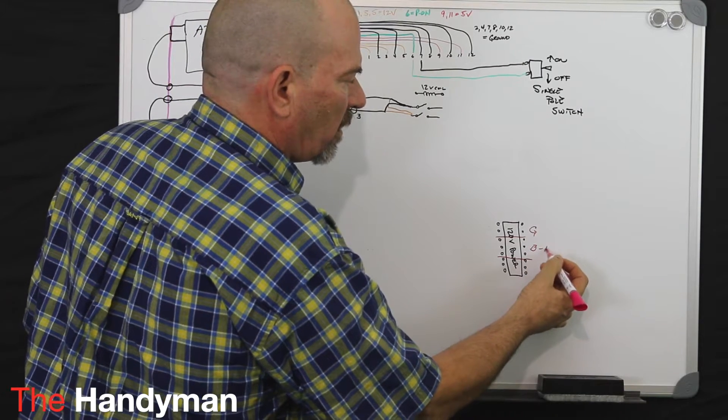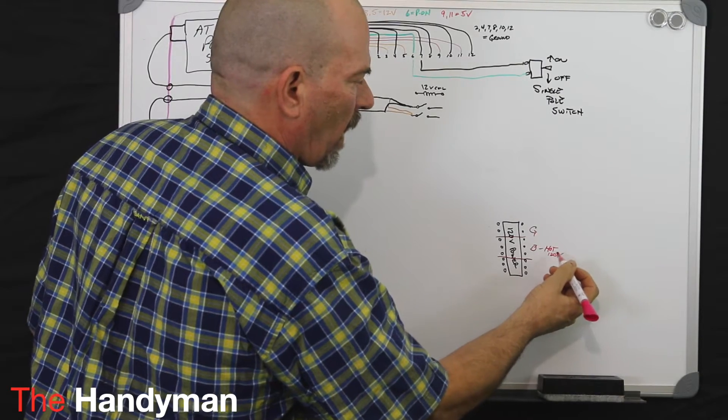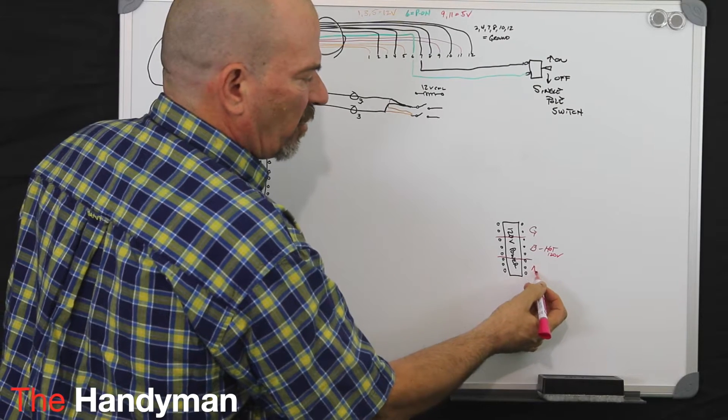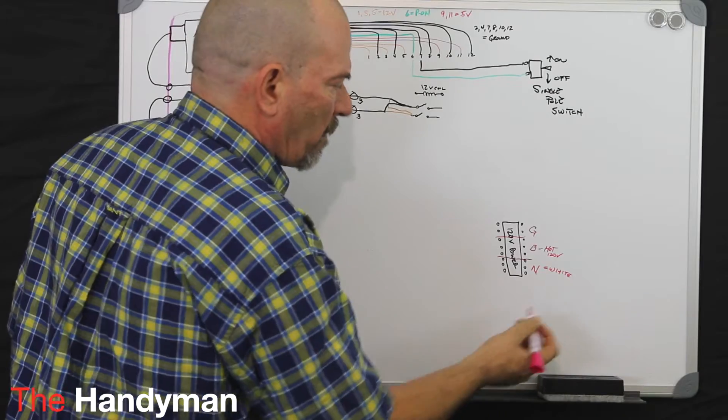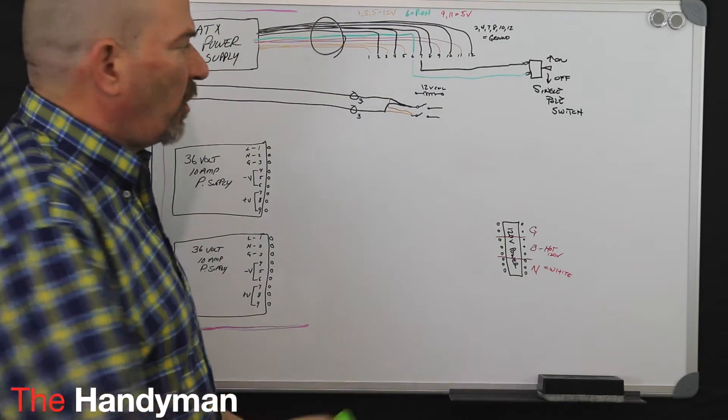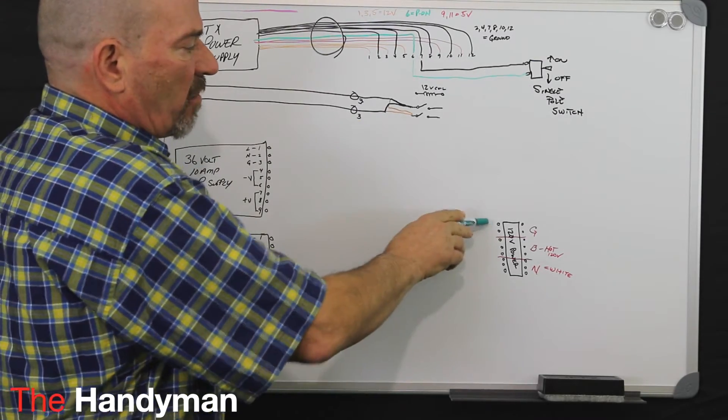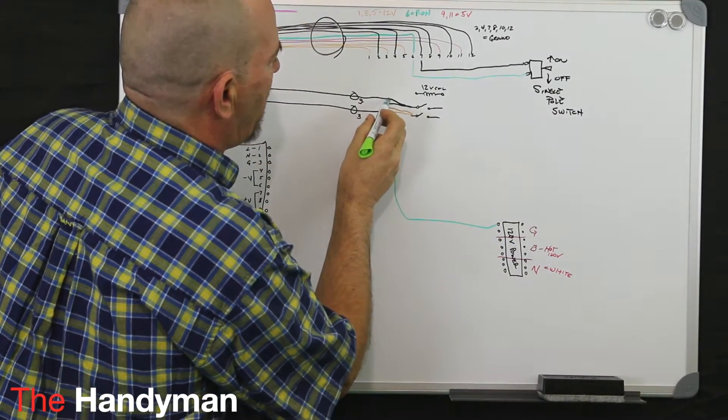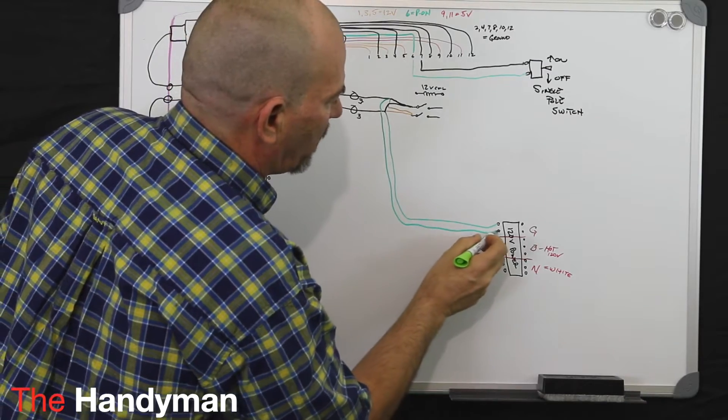Your black is your hot, your 120 volt, and then the last three screws are my neutrals or your white. So what you do is you take the grounds out of these two cables and you run them down across from your terminal strip, and it doesn't matter, you can put them under the same screw or two screws.